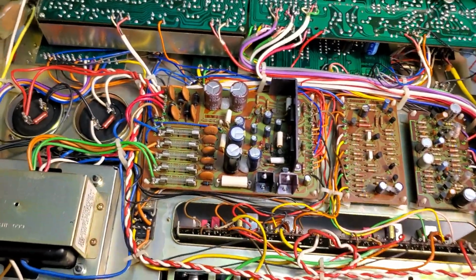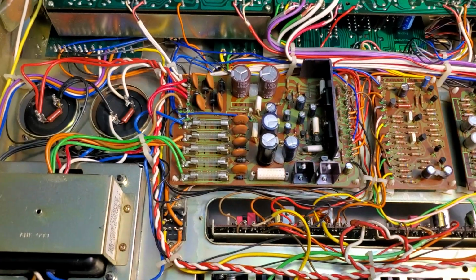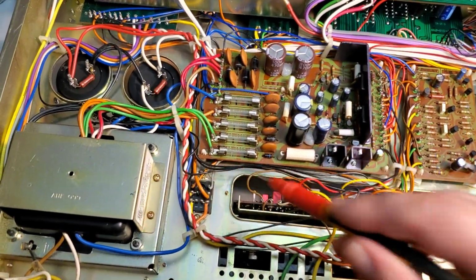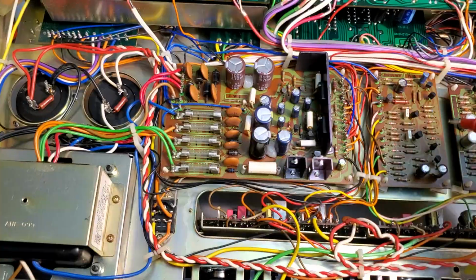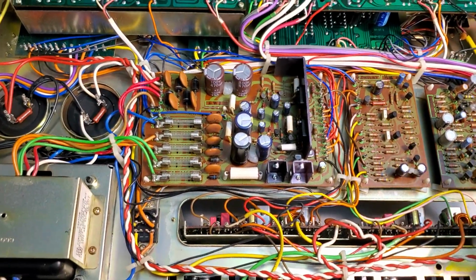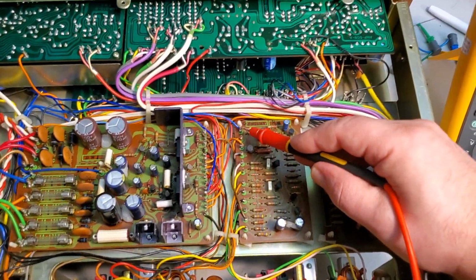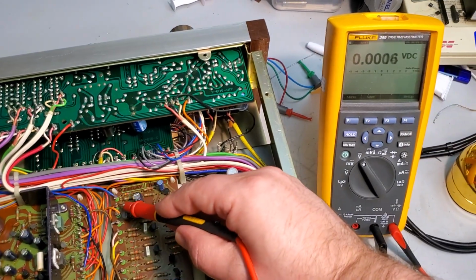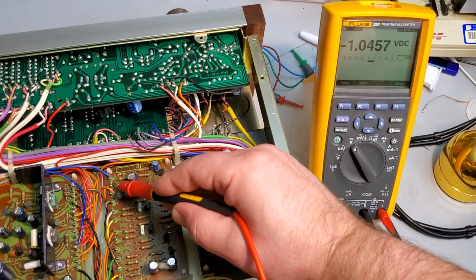So thinking I have a power supply problem, I go, okay, what voltages do I know I should have? And then I got a brainwave. The protection relay is 24 volts, so the protection circuit must have at least 24 volts on it somewhere, maybe more. So we'll just go and test all the stuff.